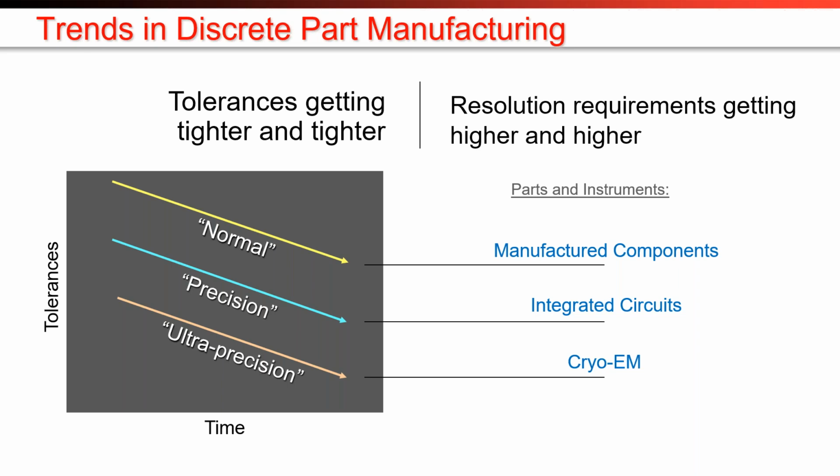NMR spectrometers, similar to Moore's law in semiconductor manufacturing, if you go back even 30 years, the most advanced ones in the world, these superconducting magnets, were just sitting on rubber pads on the floor. And since then, they've all migrated to have airbags supporting them, and then to more sophisticated self-leveling air isolation systems.